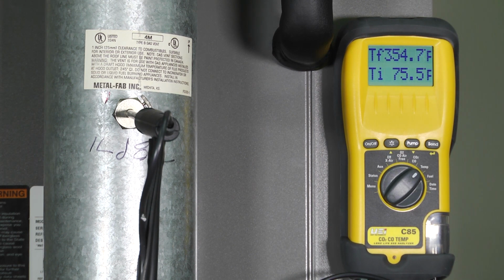Air-free means that, one of the things we have in combustion is what we call excess air. Excess air is there because we want to make sure you're going to have proper combustion no matter what happens. So as a manufacturer, and we all do it, we put a lot more air in than you actually need in order to get proper combustion. We call that excess air. Well, that excess air doesn't get used.